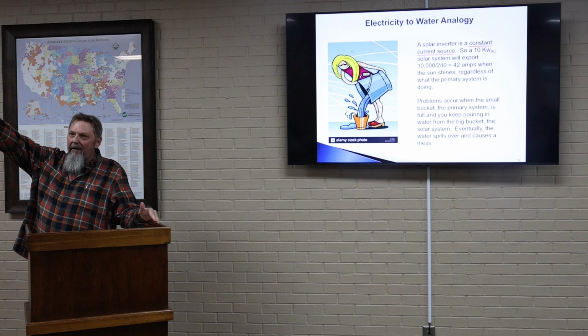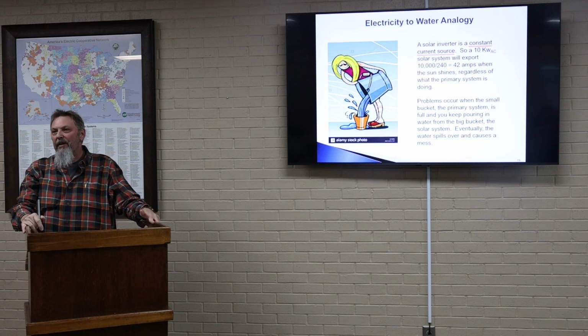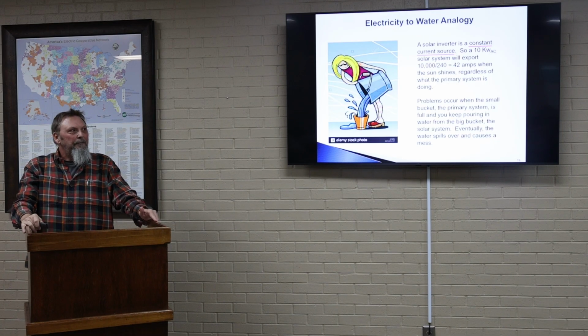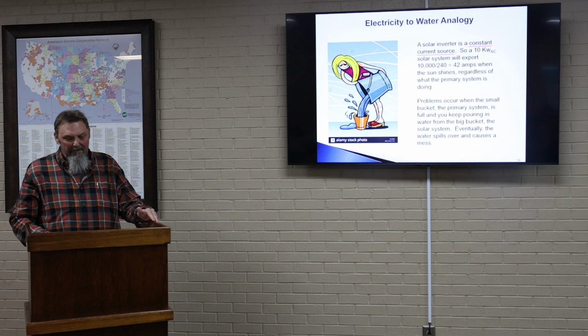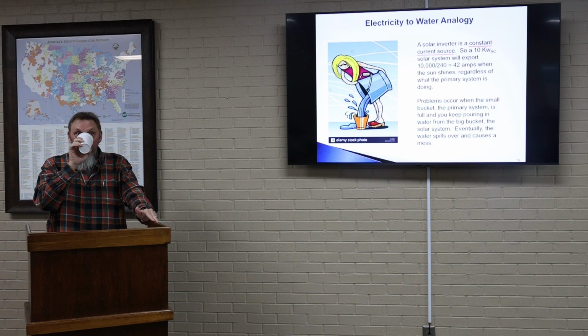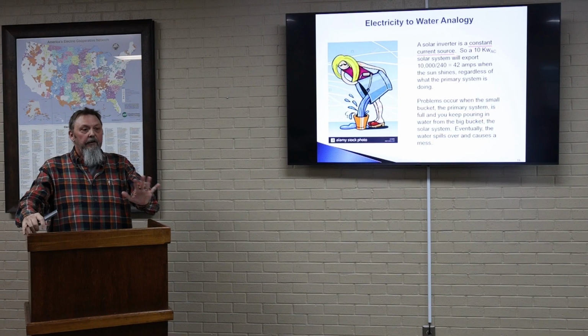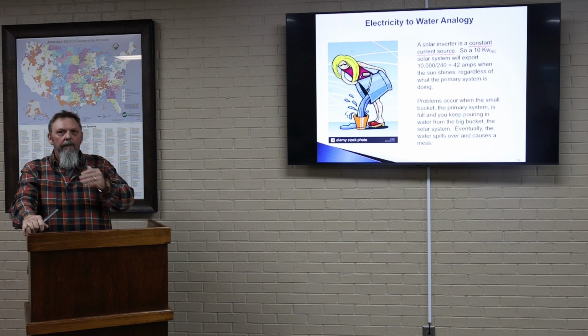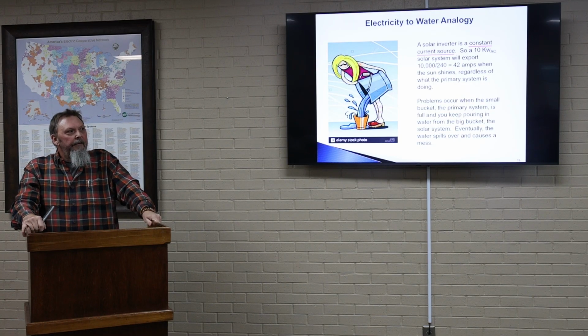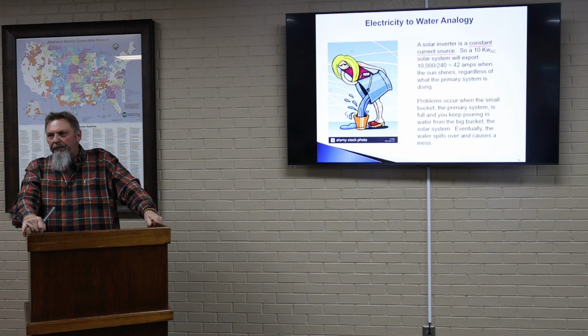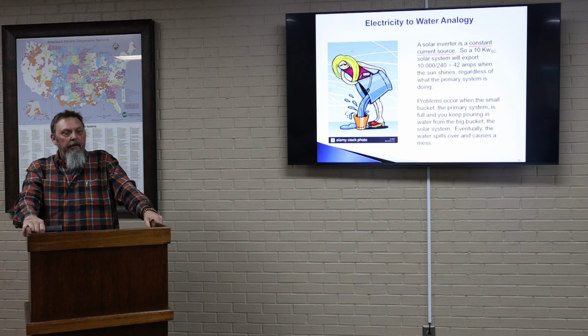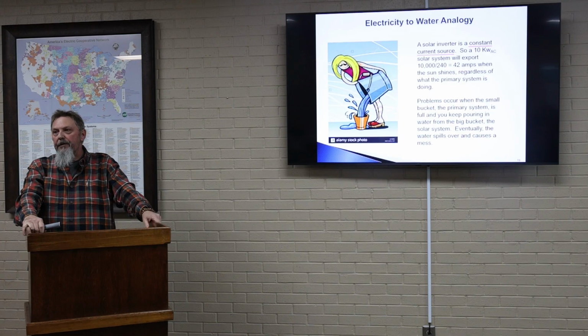If you're at the very tail end of a 30-mile long feeder on single phase, different issue. So part of the question is, the 13 kW you're producing — if your home usage can use that 13 kW, it's being utilized by your home, and that's perfectly fine. Being able to export it back onto the system is different, because someone on a single phase line way down the road, with 2 or 3 solar or net metering members, may be getting too much flow, so we've limited it to like 10 kW. Out of that 13, we can only put 10 back onto the grid. But if you can utilize the 13 you're producing for your own usage, you can use it — you could even put in 50 if you can use it.